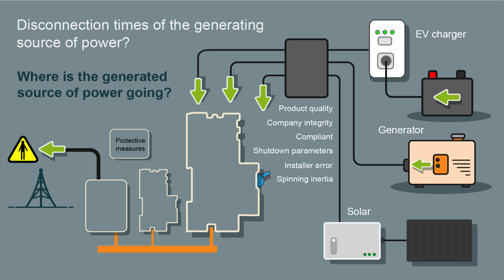This is the problem: the RCD has opened, but power is not disconnected. The opening of the RCD should disconnect the generating source of power — the inverter or the EV charger — or so you'd think. How quickly does it do it? I don't know. It's probably device-dependent and I doubt there's a single standard. There's also the issue of product quality and company integrity. Are these inverters fully compliant? On some, you can have shutdown parameters which you can change, so you might get installer error. You might also have mechanical devices with some spinning inertia. There are plenty of things which might affect how long it takes for power to stop feeding these RCBOs.